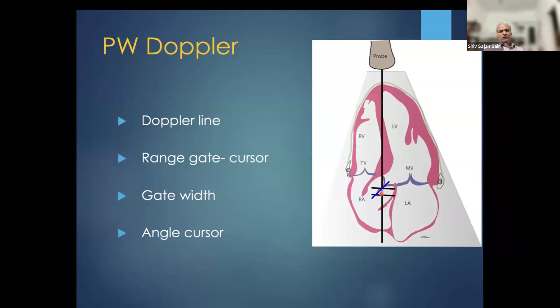So now let us come back to our transmitted signal and received signal. Because the machine is processing signals between these two range gates only, suppose this is the signal which was passing through the range gate, and this is the remaining signal. This is again range gate, remaining signal, and this is how it is going. And again, this is hitting the anatomical areas and coming back. So the machine will overlap them. And you know that here there was no actual signal, but the machine knows that possibly this was the signal which was sent, which is fairly constant. However, the transmitted signal may be different.